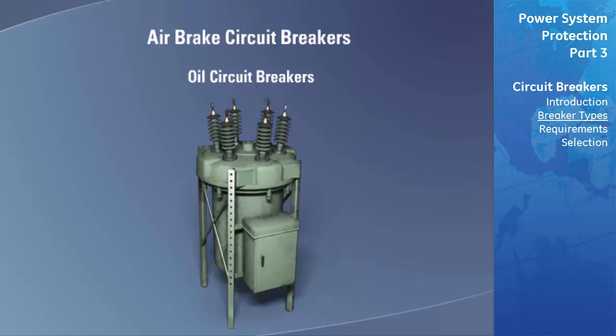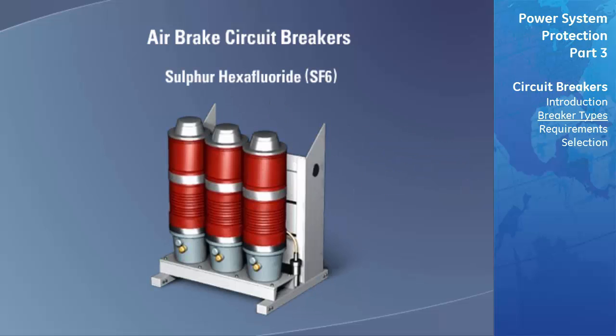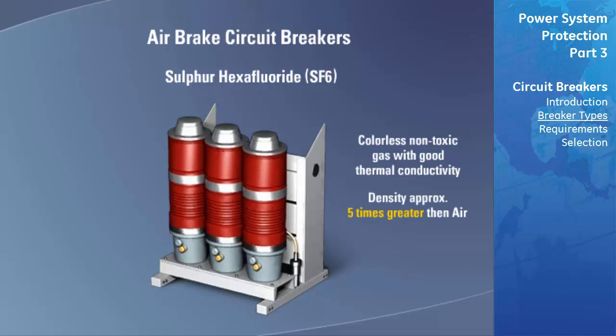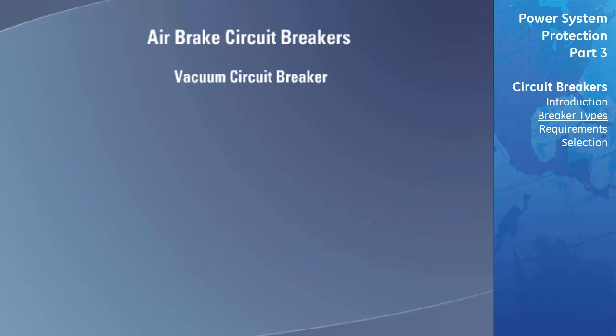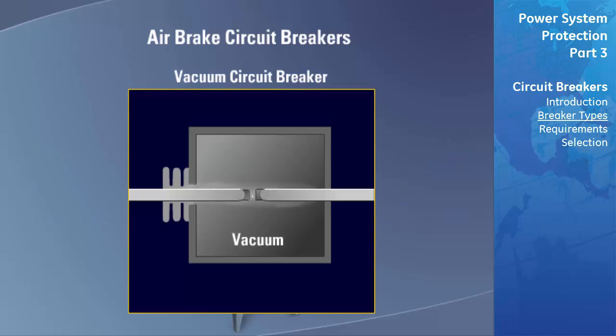Sulfur hexafluoride (SF6) gas is an alternative to air as an interrupting medium. SF6 is a colorless, non-toxic gas with good thermal conductivity and density approximately five times that of air. It is chemically inert up to temperatures of 150 degrees Celsius and will not react with metals, plastics, or other materials commonly used in high-voltage circuit breakers. The principle of operation is similar to air blast breakers, except that SF6 gas is not discharged into the atmosphere.